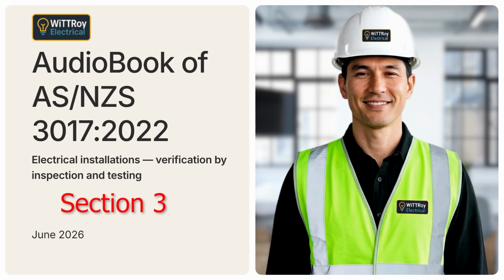This is important because once an installation is energized, some risks may increase. It is better to find visible defects before supply is connected. The clause also reminds us that some parts of an installation may not be visible after the work is finished. For example, cables may be hidden inside walls, under floors, in roof spaces, in concrete, or underground. If a part of the installation cannot be inspected at completion, then it should be inspected during the installation work, before it becomes covered or enclosed. In simple terms, do not wait until the end if the work will be hidden later. Inspect it while you can still see it.